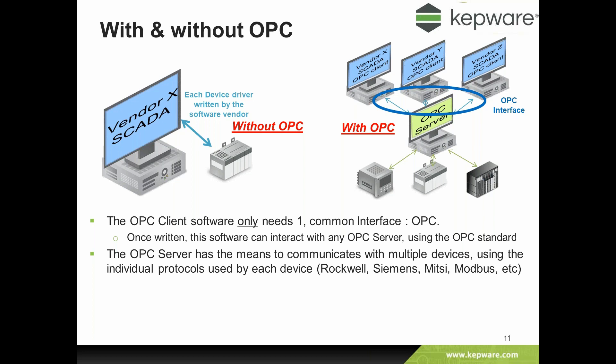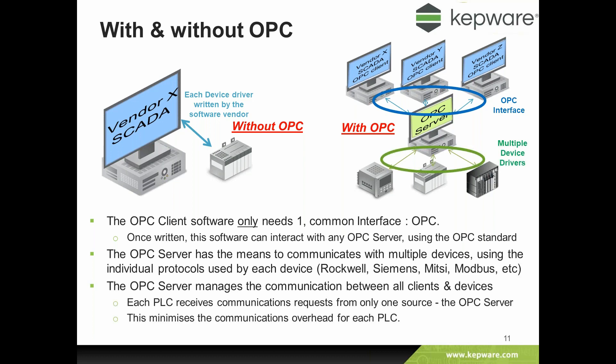The OPC server manufacturers need to continually update their server products to keep track of different changes and new models launched onto the market. That means a single OPC server can communicate to many different types of devices — in the PLC world, for example, talking to Rockwell, Siemens, Mitsubishi, Modbus, Omron, and many other vendors all within the same OPC package. The OPC server manages communications on one side to SCADA or OPC client applications, and on the other side down to each device, so an individual device only sees requests from a single point — the OPC server — minimizing comms across the network.